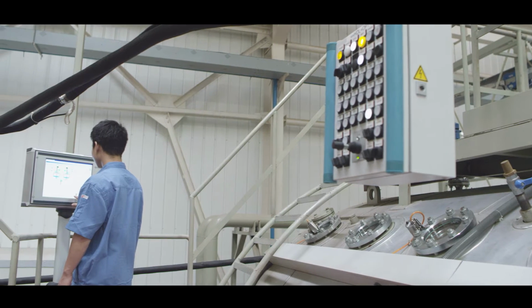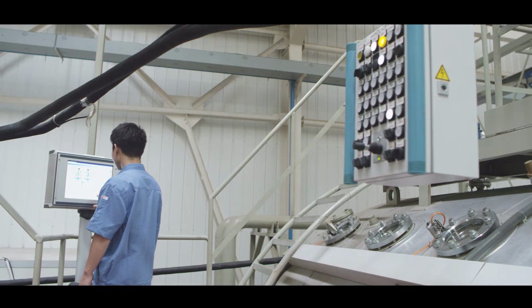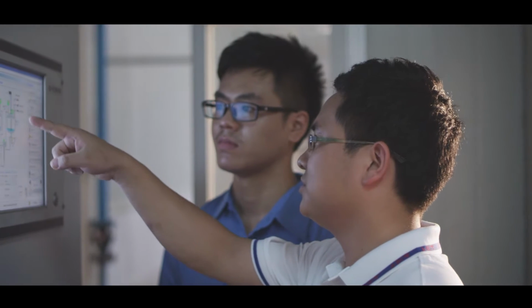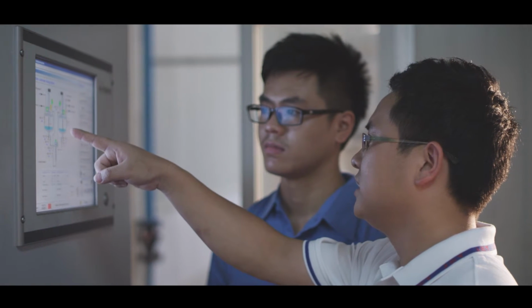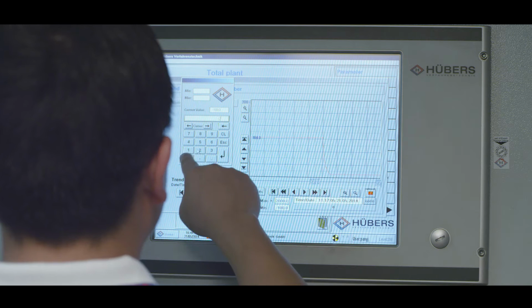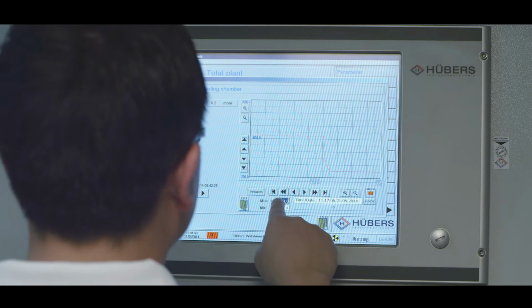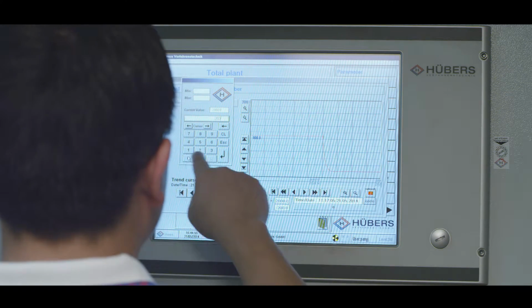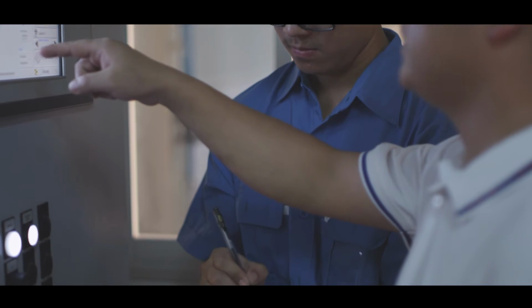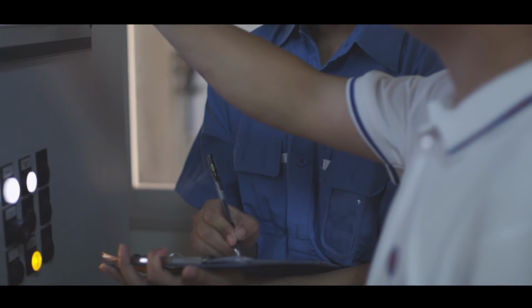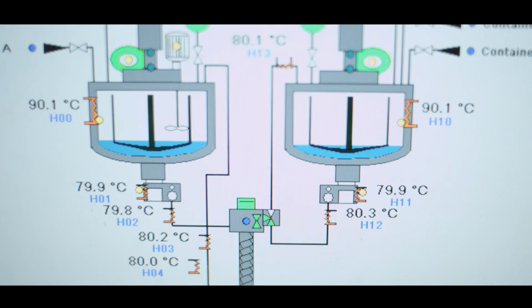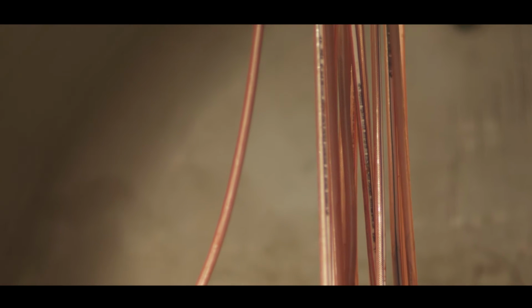One element of the process unique to coils casted at JST is the method used to mix the epoxy resin and the hardener. Most common to the industry is a method called dynamic mixing, which basically batch mixes both parts prior to injection into the molds. In the interest of more uniform curing and producing a casting with a higher degree of integrity, JST has chosen a superior static mixing process. Both parts are mixed in the injection head as they are being poured into the molds.